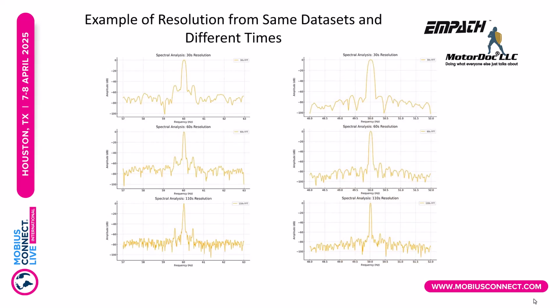Now, why is resolution important? Well, because there's a lot going on because you're seeing everything at once. It's not like vibration where I can have a resolution or a bin size of 60 CPM or 1 hertz. I have to get down into fractions of a hertz. So that 0.008 or even 0.01 becomes really important if I want to look at low loads as well as heavier loads, and we'll talk about that in a second.